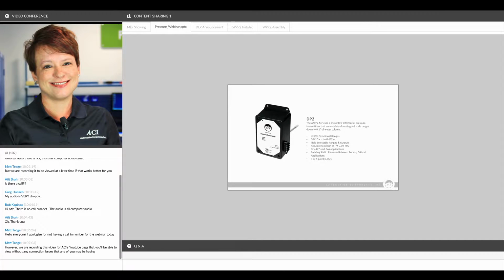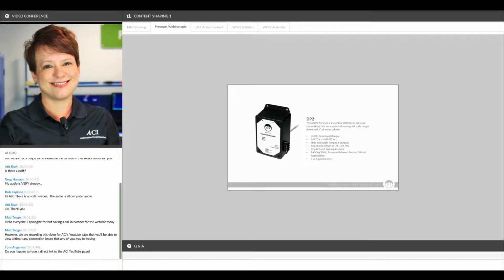We also have a DP2. This one's going to be uni or bidirectional, so positive or negative pressure capability. The lowest pressure range available is 0.1 inches of water column, good for ranges up to 0 to 10 inches of water column. Again, it's range and output selectable. Output choices on this one are 0 to 5 volts, 0 to 10 volts, or 4 to 20 milliamps.